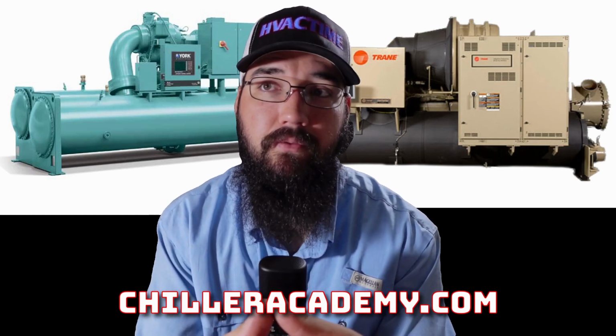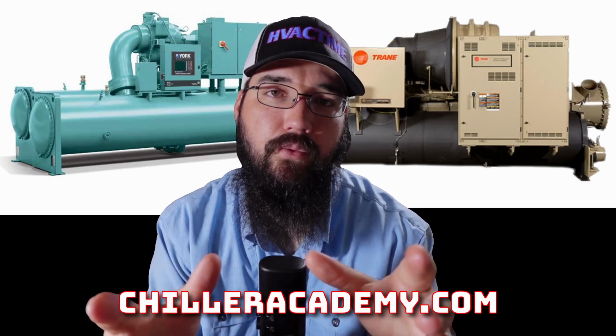Anyway, low pressure, high pressure, really important to understand the fundamental differences. Most of what happens inside of the chiller doesn't change a whole lot, okay, between the two styles. So our overall compressor, our overall centrifugal theory, refrigerant theory, very little changes in between each type. It's about when we get into things that are specific that we need to be more mindful of, such as the purge system, such as the physical pressures we operate at, and the leak searching. You know, there's a whole leak search process with low pressures that you don't need for high pressure because, well, we have to pressurize the machine and we have equipment to do that with. We'll talk about those things. But the nice part is the vast majority of what there is to share is going to be interchangeable between low pressure, high pressure. That was part of my main point there. Anyway, let's roll on with lessons.